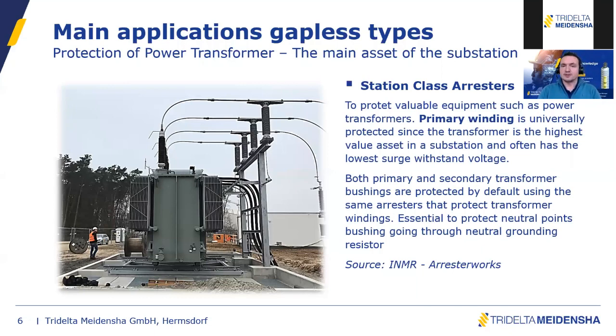This is, of course, a very expensive and critical component that you don't want to be damaged due to over voltage. And also, quite often, the transformer windings have the lowest surge withstand voltage. And also, both the primary and the secondary transformer bushings are protected with the same surge arresters in general. And sometimes if you have neutral point bushings, it's also common to use surge arresters.